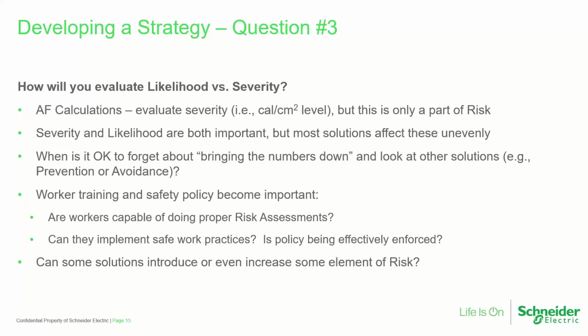Now, another thing I've seen, based on my own experience, a lot of folks look at different solutions and they think, okay, if I can't bring the number down on my arc flash level, if I can't bring the calories per centimeter squared down, then this is not a solution that I want to pursue. I don't think that's a really valid way to look at this, or at least it's not the ideal way. There may be cases like we just talked about with the infrared scanning. When is it okay to forget about bringing the numbers down and look at remote operation, look at thermal sensors, look at whatever else, in order to functionally eliminate the risk to the workers, and continue to allow those energy levels to be a little bit higher? Just again, something to think about.